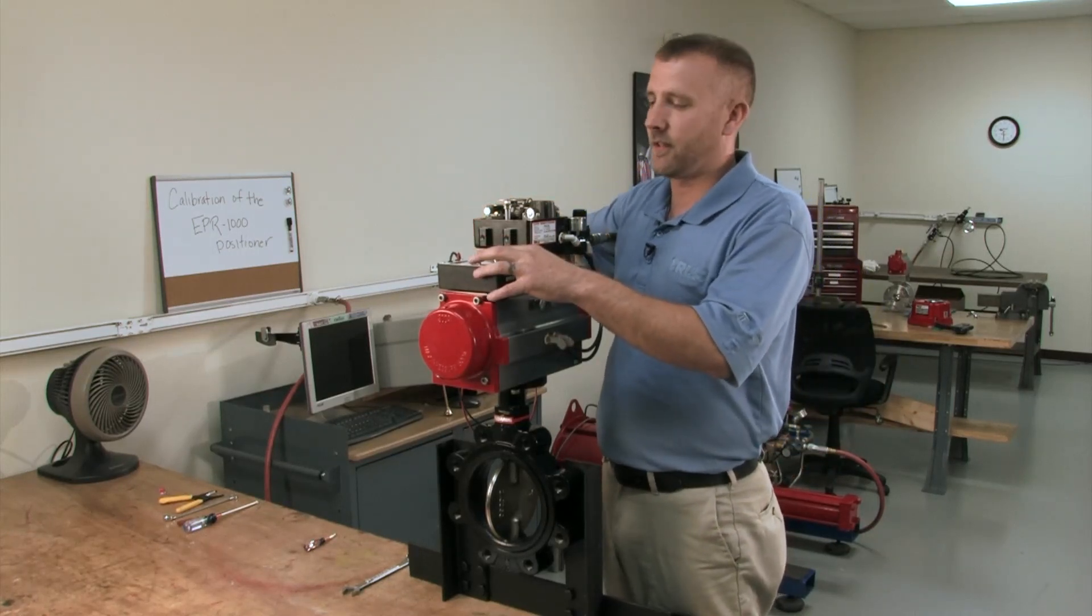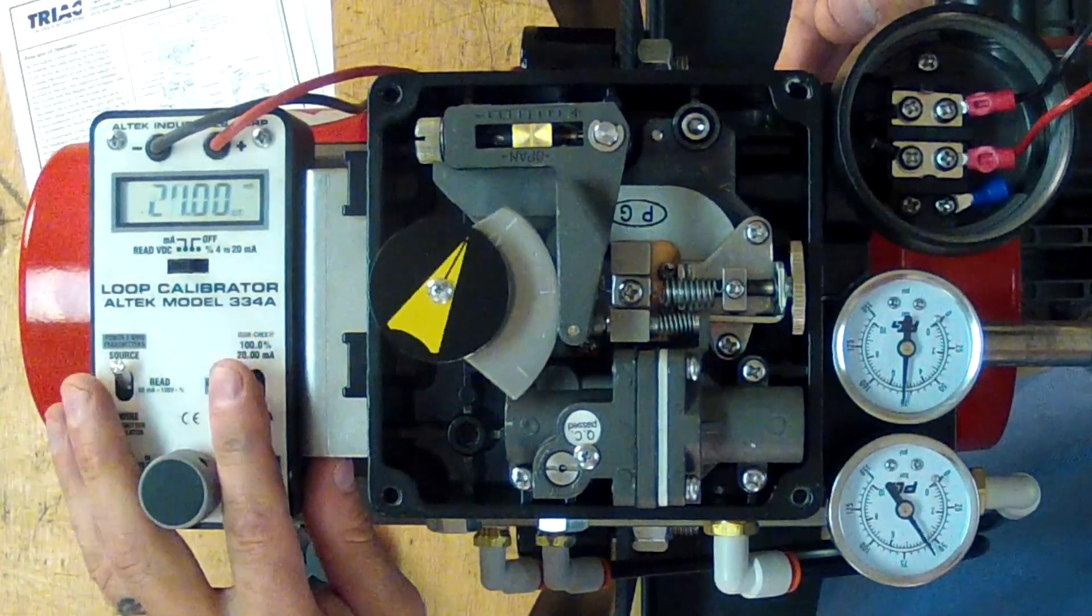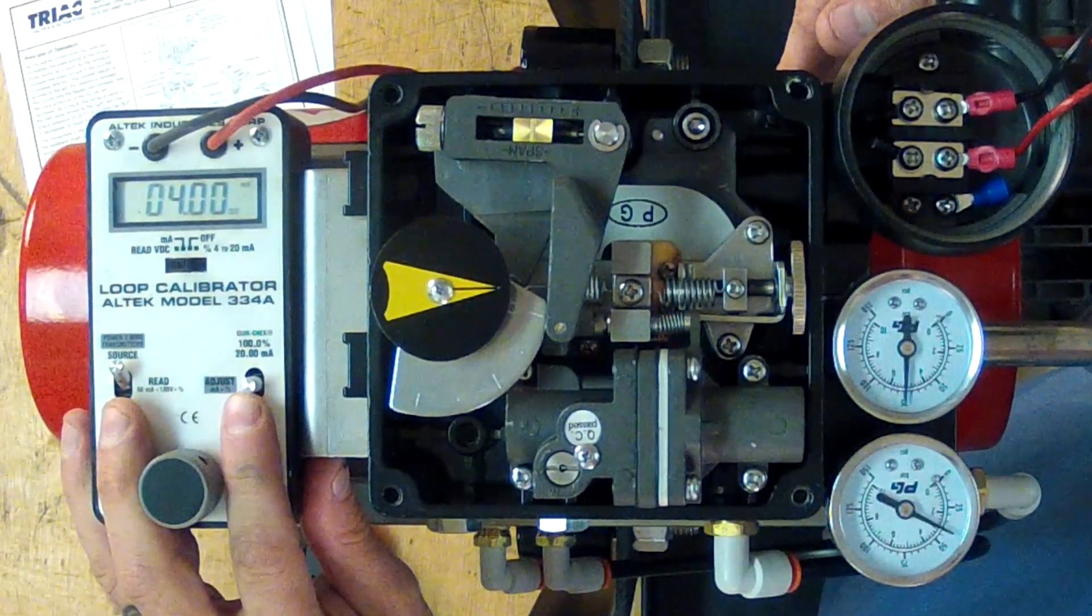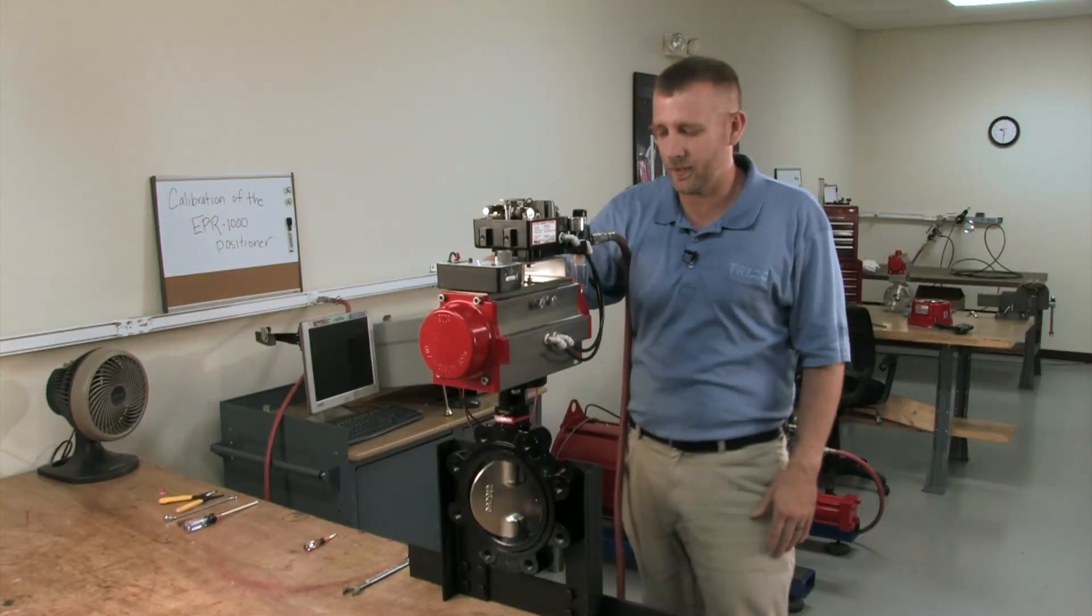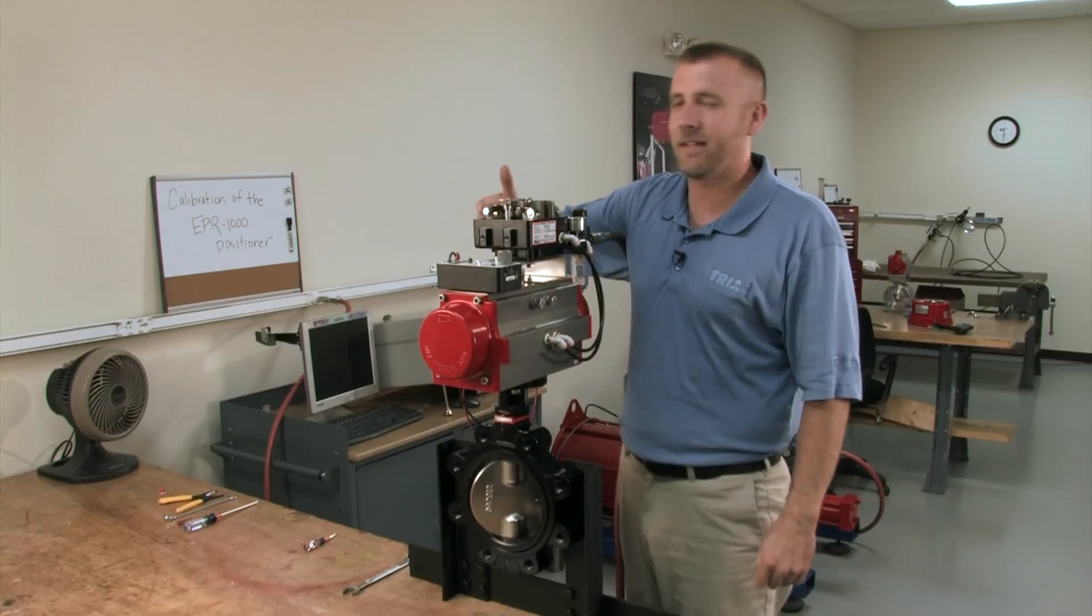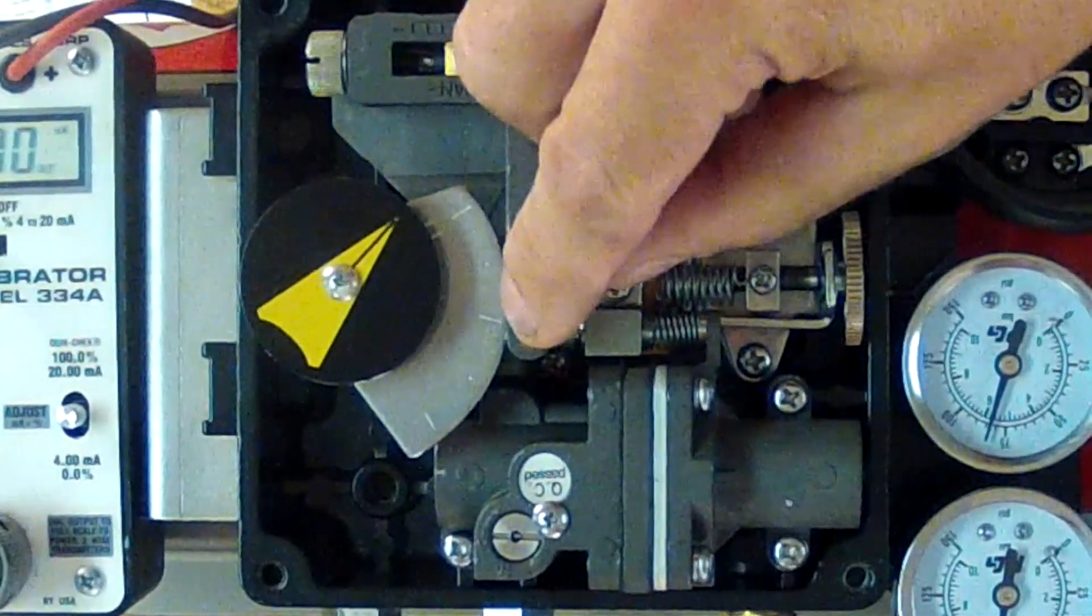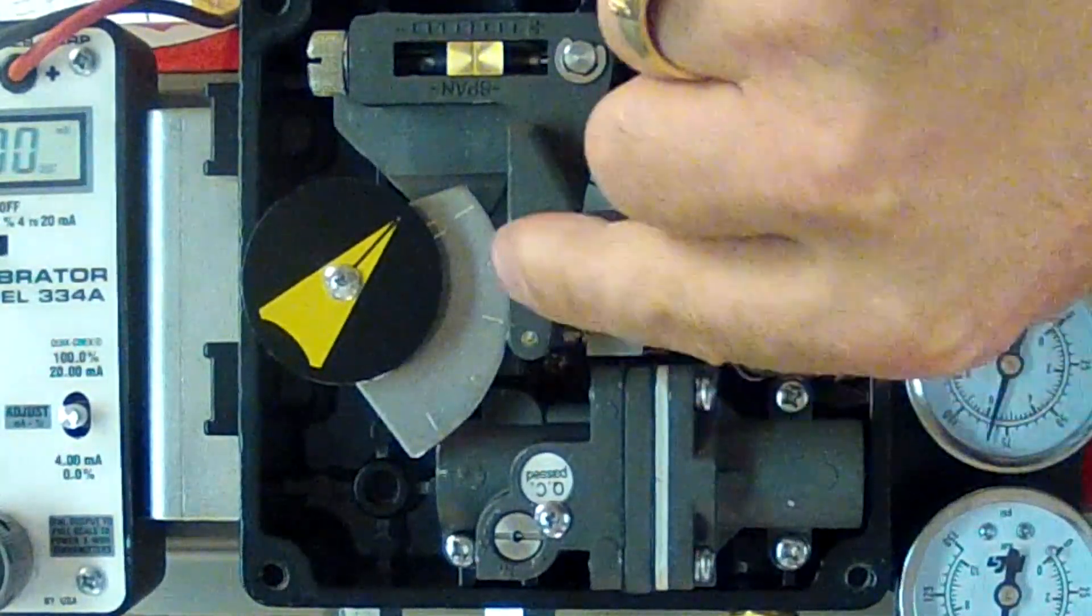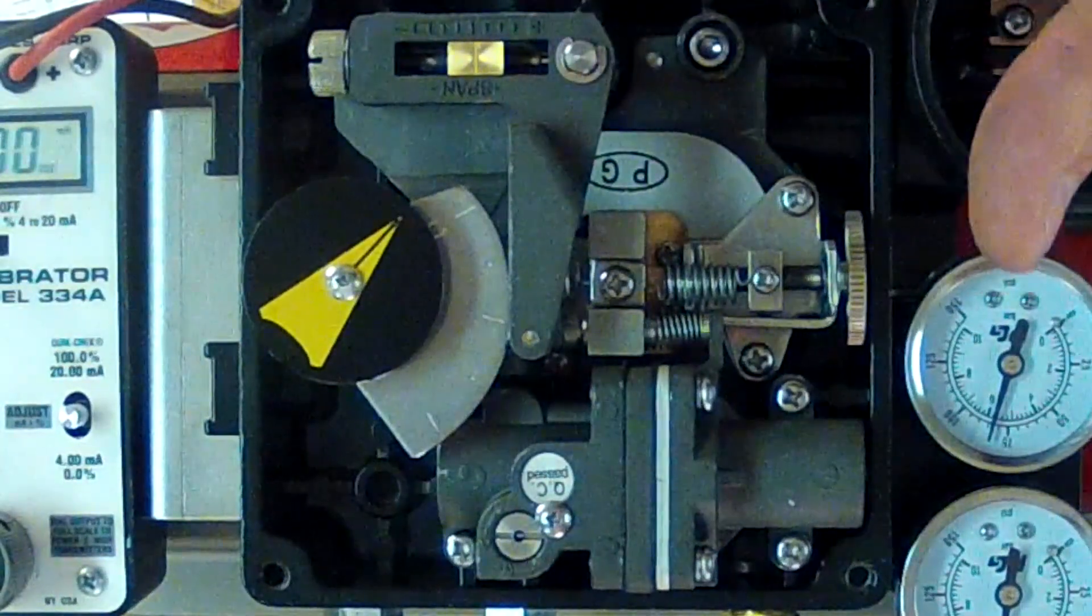Now, we're going to check our mid position by going back down to 4 milliamps, then to 12. Now, what you're looking for in your mid position is a nice 45 degree angle on our disc. Or if the package is in line and you cannot see your disc or your ball in your valve, a reference point on our travel cam is the mid line here. Should be somewhere in line with the bearing. It doesn't have to be perfect, but that's just a reference point.